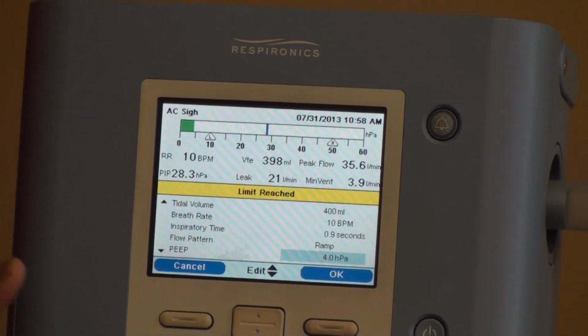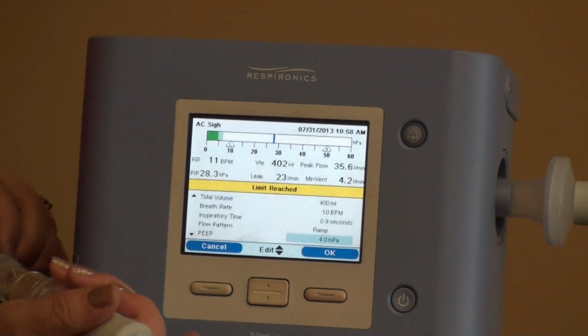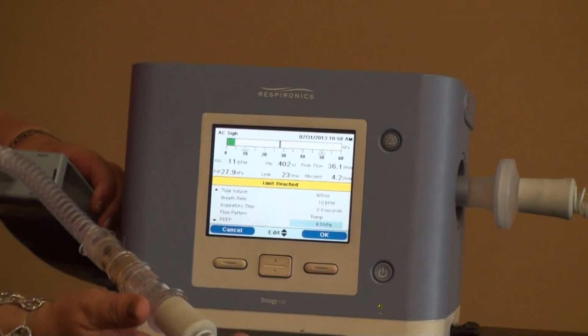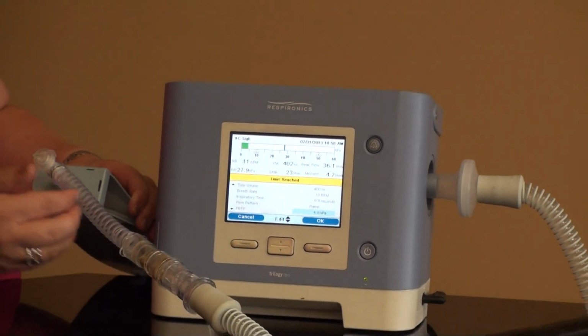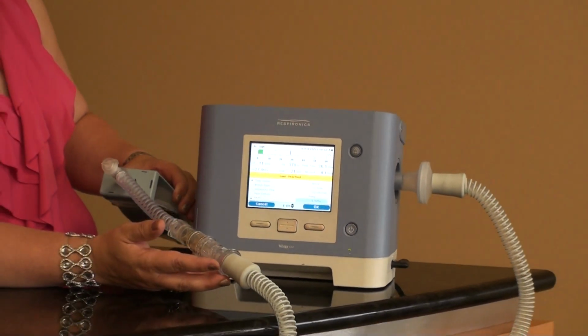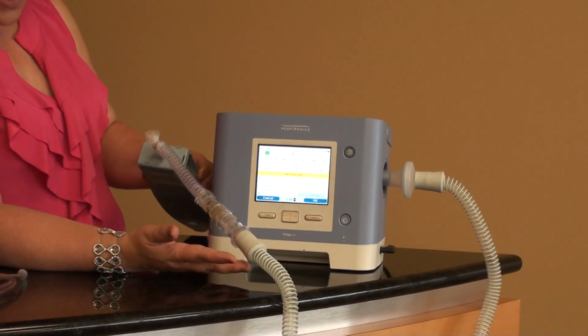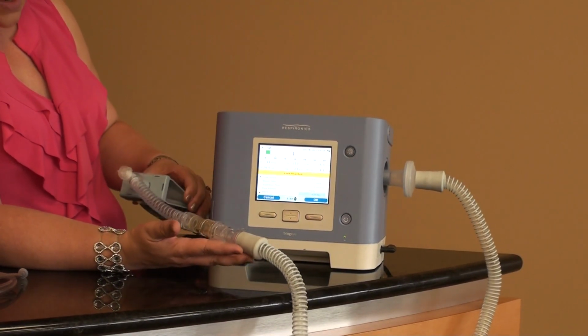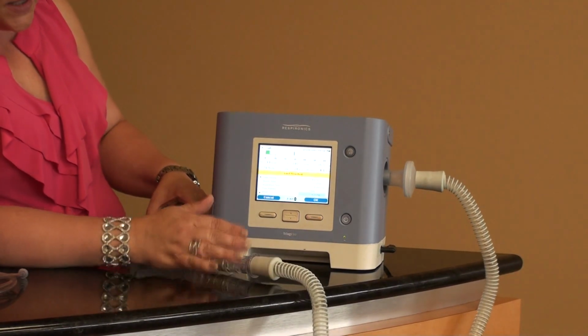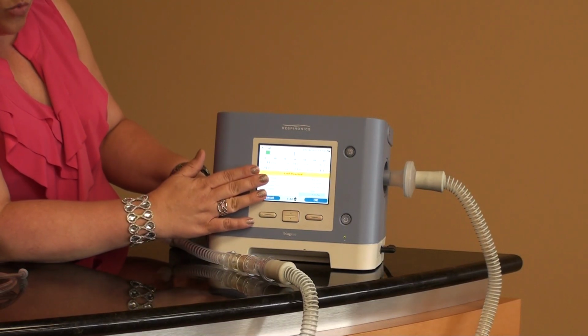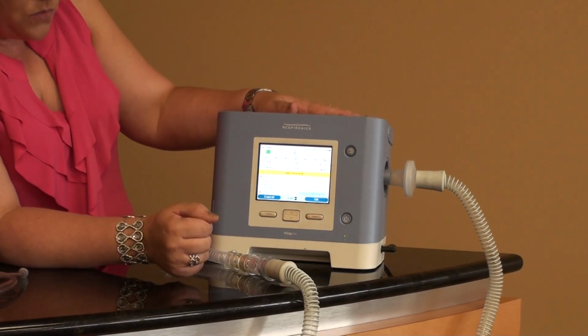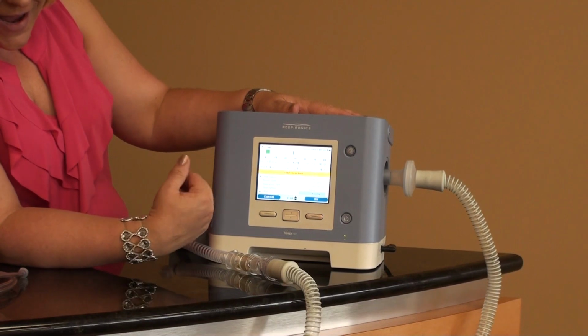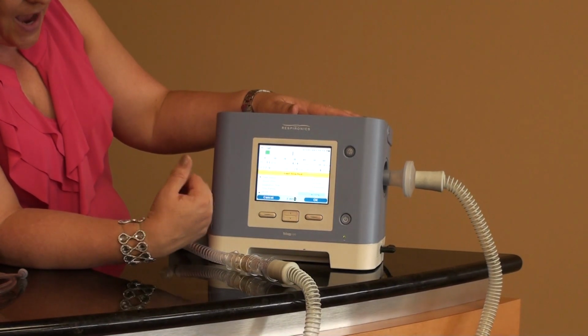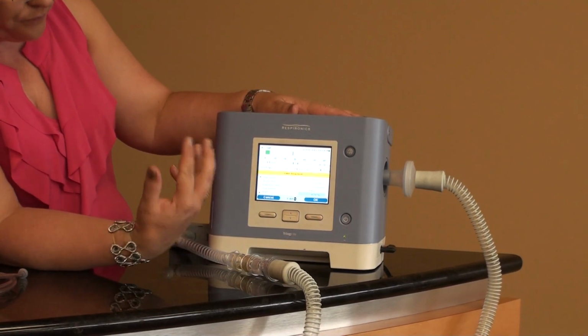Because it is a passive circuit on here, and because I have air constantly going through here, I have to have a PEEP of 4 coming through at all times to flush out the CO2. Well, I wouldn't know that, and how would anybody know that unless you've dealt with this machine quite a bit? So it is a safety check. It's like, oh no, I can't do that. So then you would just call the physician and say, I can't set a PEEP of 3 on this. It has to be at least a PEEP of 4.